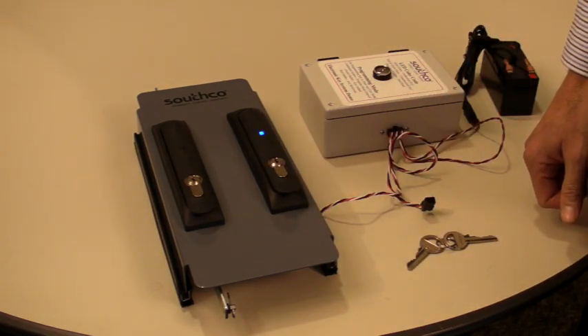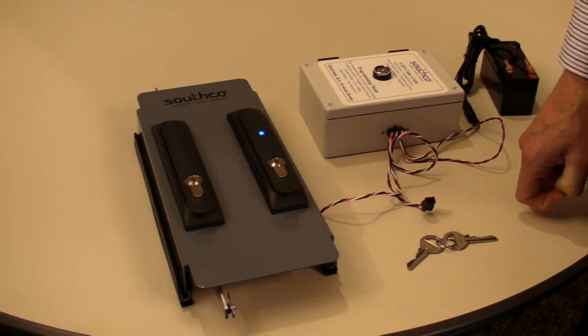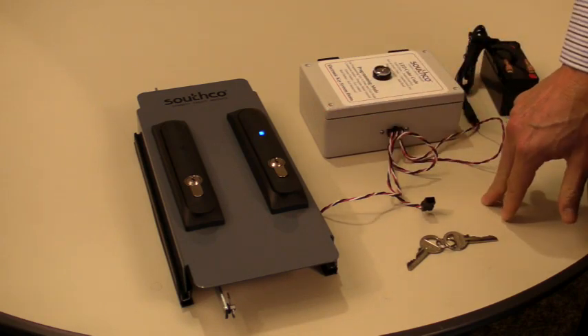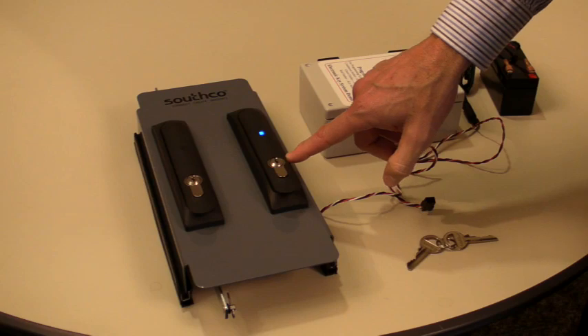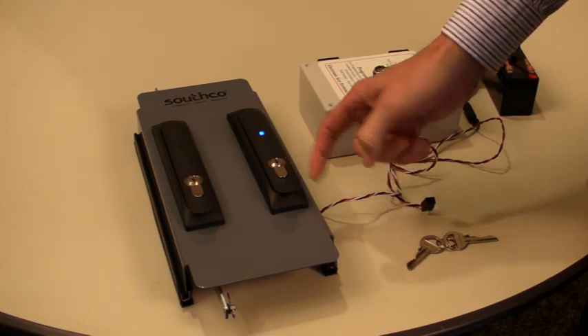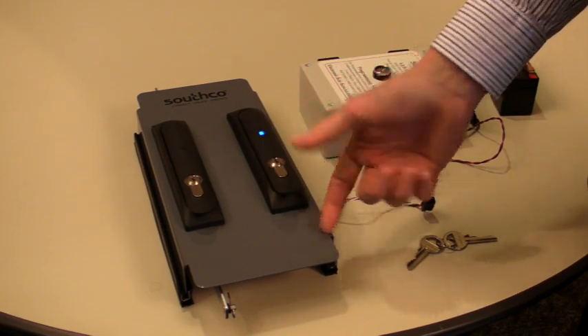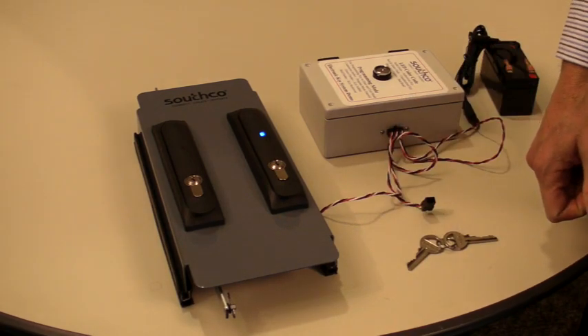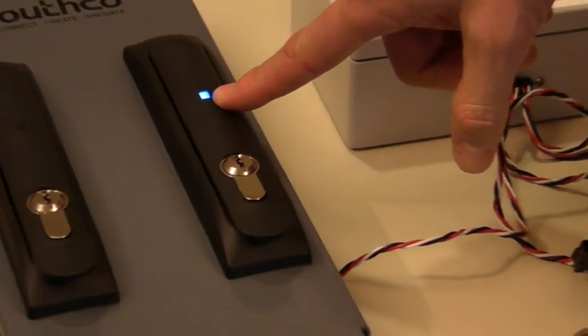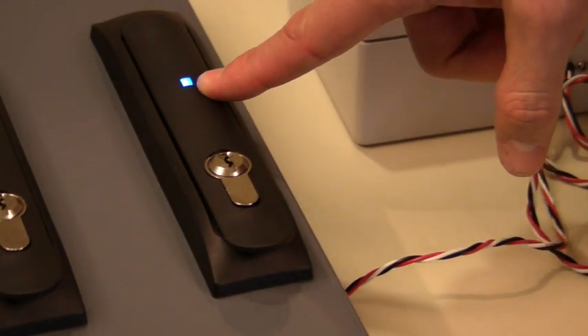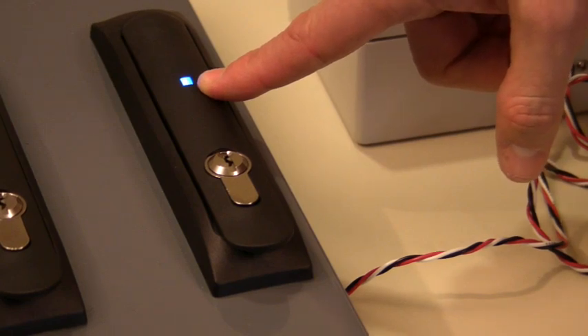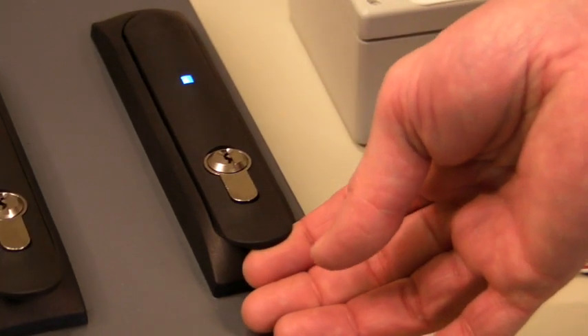You'll notice in this position it's giving me a warning that says that either intentionally or accidentally, the handle is, although closed, not in the latch position, so someone could come along and lift. As soon as I push it beyond the detent, I get my solid blue which indicates that the latch is in the locked and latch status, and now it is completely secure.